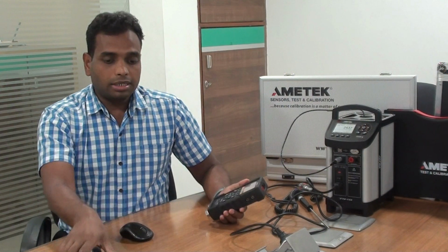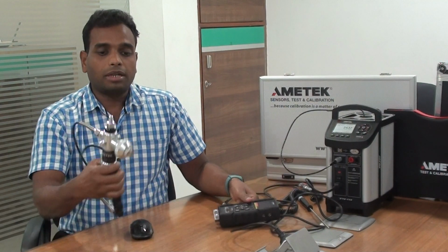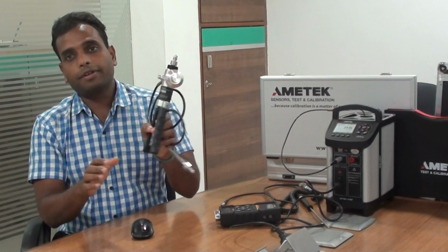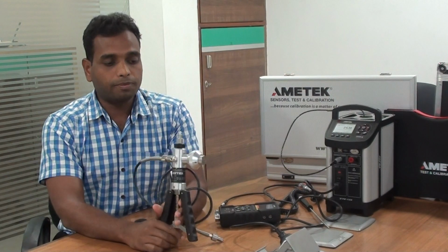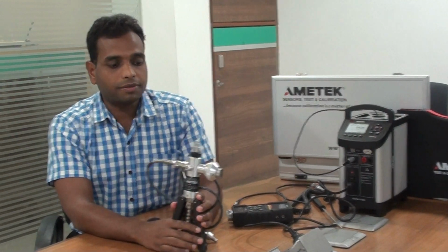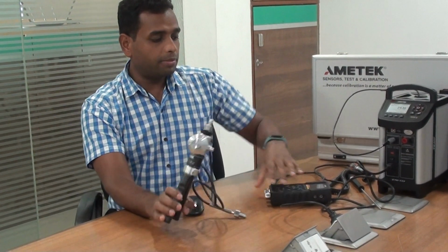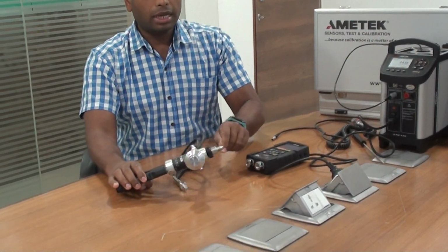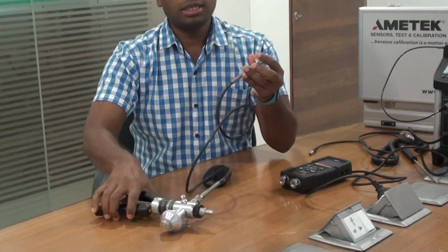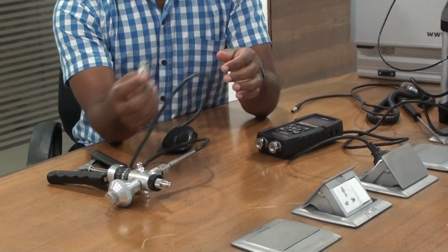For these inputs, we are using the T975 pressure pump, which is pneumatic pressure from vacuum to 40 bars, connected to one of the inputs. The other side uses CPF fittings, which connect to the DUT side.